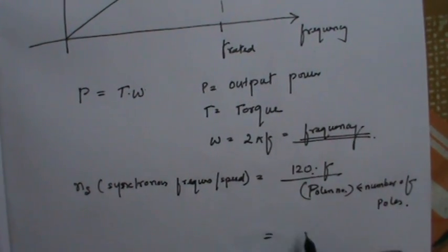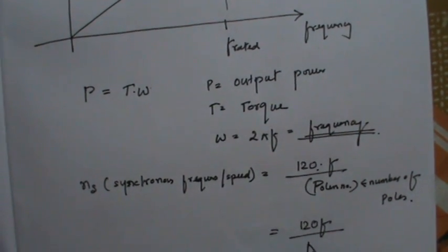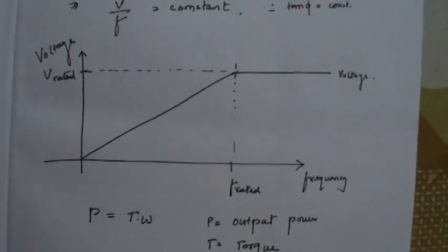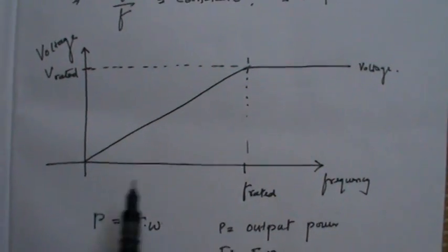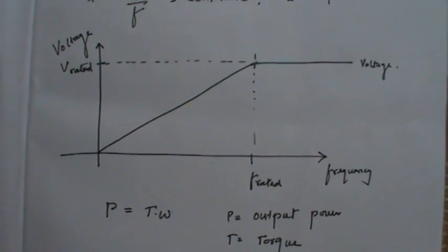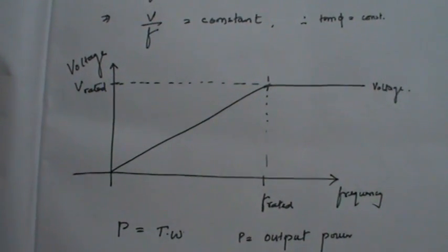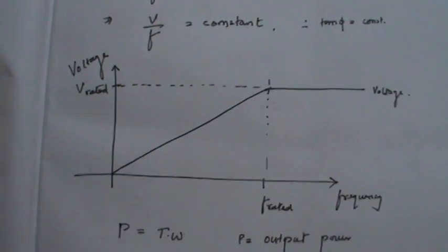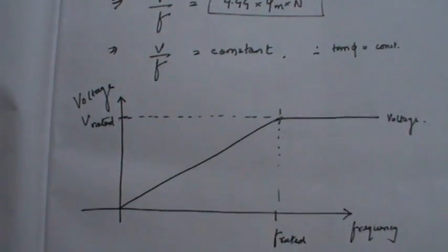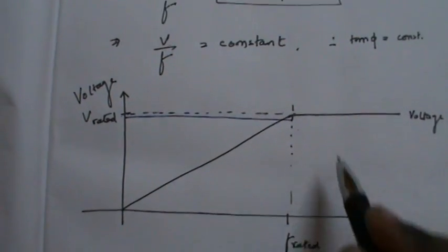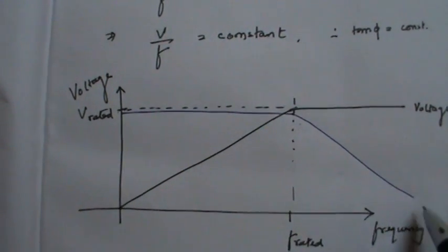Coming back to the graph: the horizontal axis is frequency and the vertical axis is voltage. Now I will draw the torque curve. In the region below rated frequency, the voltage is increasing while V by F is constant, which means the torque in this region is constant. After the rated frequency, the torque will decrease. So this is the graph of torque versus frequency.